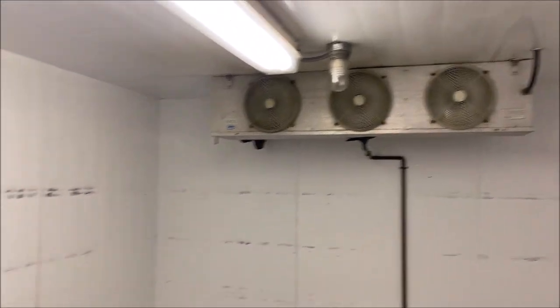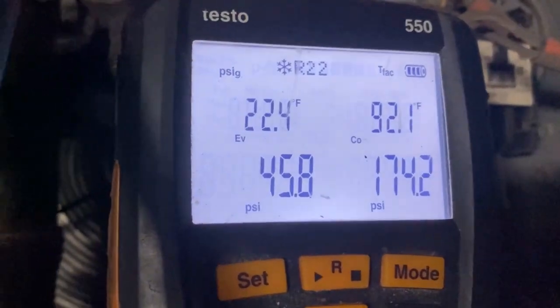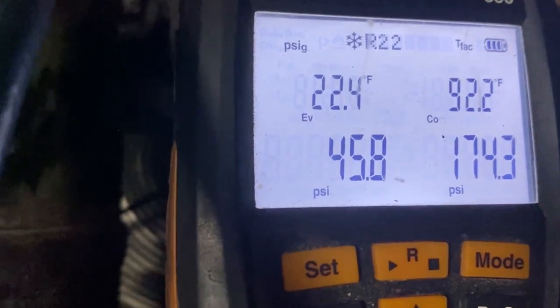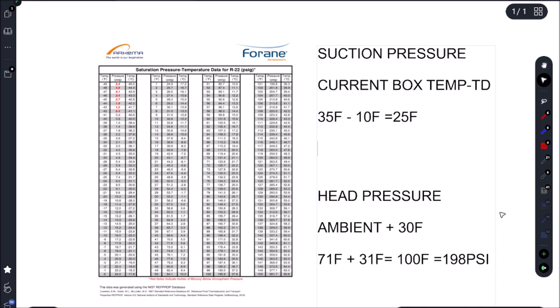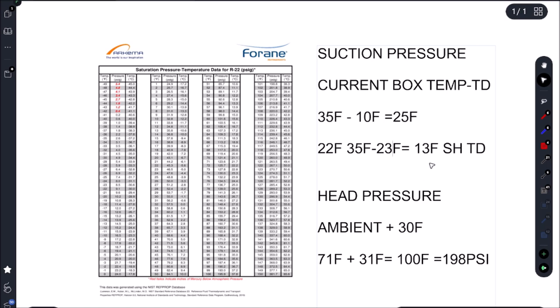So our final temperature 35 Fahrenheit. Okay, we've cycled off at 22 Fahrenheit. Alright, so let's go see what pressures we're actually looking for. So we're going to subtract our superheat or evap TD which gives us 25 Fahrenheit. Okay, we had 22 Fahrenheit saturation. So if we go 35 Fahrenheit minus 22 Fahrenheit that would give us a 13 Fahrenheit superheat or TD. But really when we're measuring on the copper it's usually going to be one degree higher. So this becomes a 12 Fahrenheit superheat TD and we're running about a hundred feet. So this may have gone up an extra degree. Now I can't check the superheat at the condenser because I can't gauge up there.